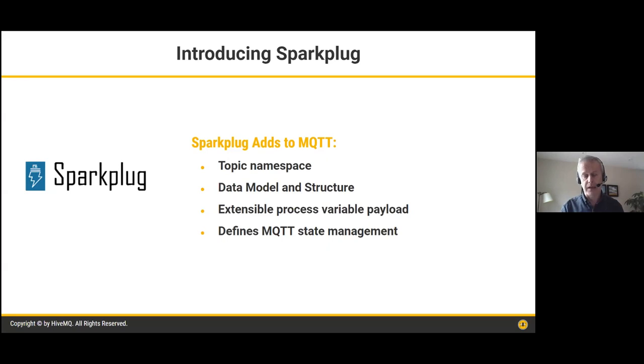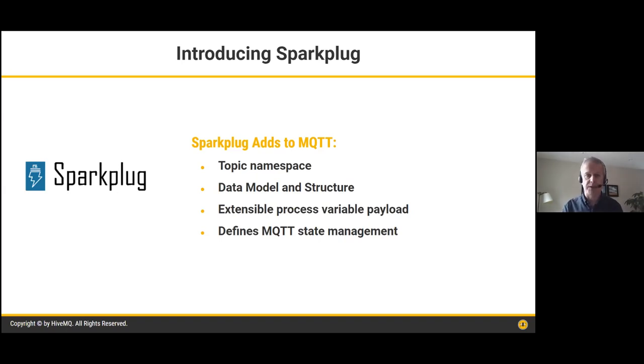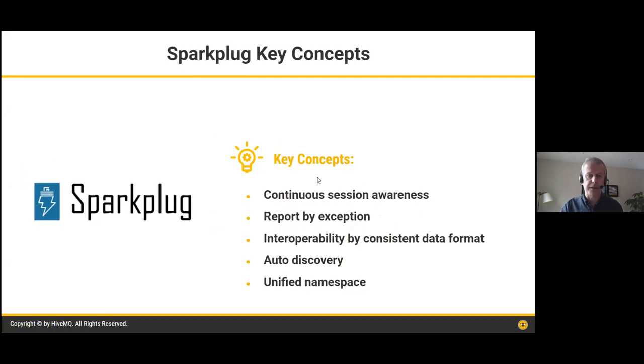However, MQTT itself is just a lightweight protocol, and by nature that is its power — but it doesn't add a lot of context to the data. For a truly interoperable system across different vendors, you need data with context, and this is where Sparkplug comes in. Sparkplug is a standard specified at the Eclipse Foundation. It adds a consistent topic namespace for all devices to publish on and all applications to subscribe to, plus a data model and structure. It also enables extensible process variables and defines MQTT state management — when a device joins or leaves a system, the appropriate birth and death messages are conveyed.